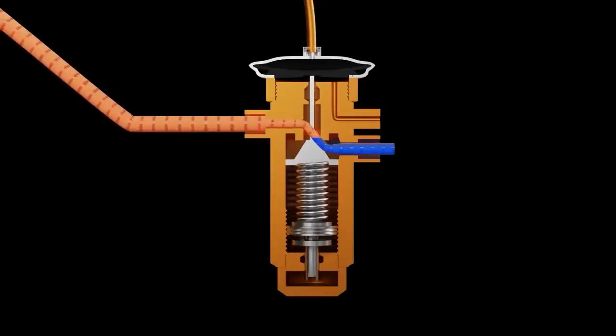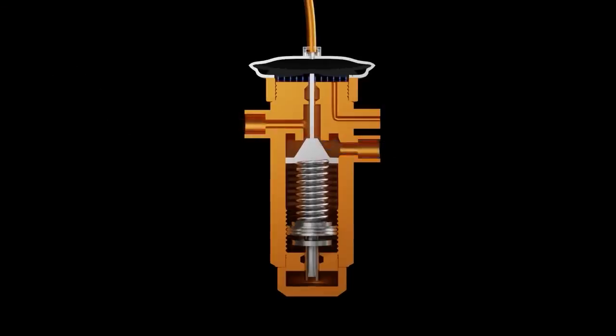Does anybody know why that happens? It's the TXV — the external equalizer is the closing force for the valve. That external equalizer is just a pressure tap into the end of the evaporator coil, into the suction line. As that suction line pressure keeps increasing, the valve closes and closes until it slams shut. That's the nature of a hard shutoff TXV — and all modern valves we work on in air conditioning are hard shutoff TXVs.